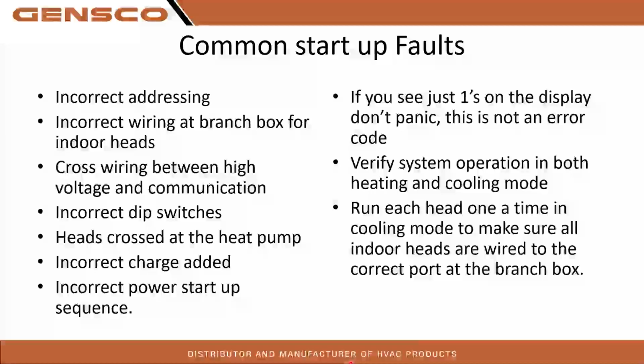So very, very commonly, guys will accidentally swap the wiring at the heat pump or the branch box with another head. What ends up happening is, for example, head A starts calling, but it's wired to port B at the heat pump or the branch box and starts sending refrigerant to the wrong head. In heating mode, it is very, very difficult to detect this, because anytime you're running in heat mode, you're sending hot gas to all indoor heads. In cooling mode, you're hitting your expansion valve before it gets to the head, so it's a different story.